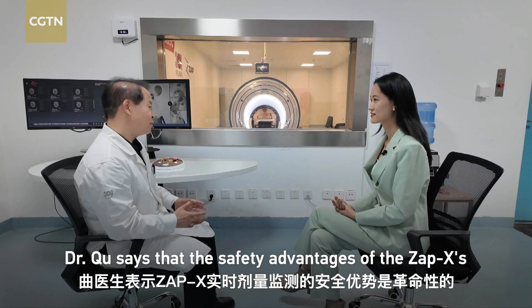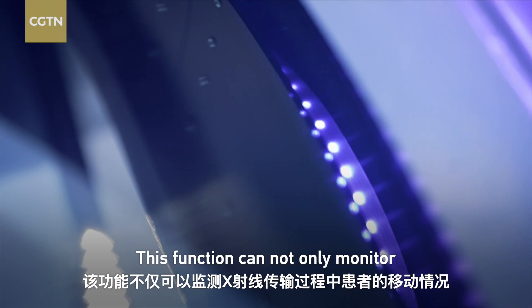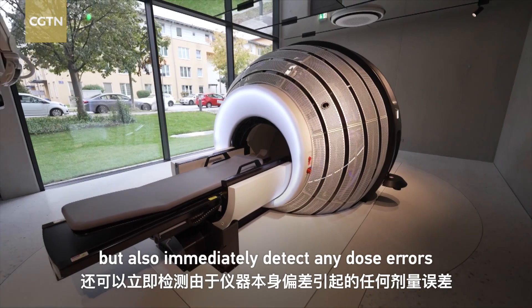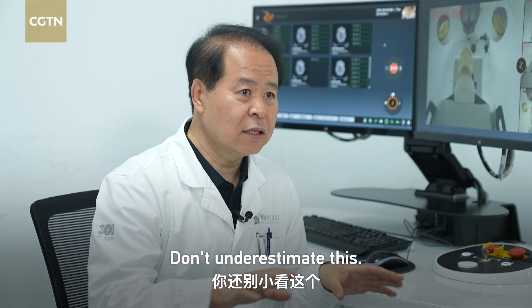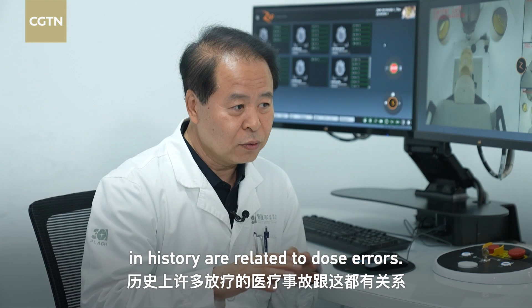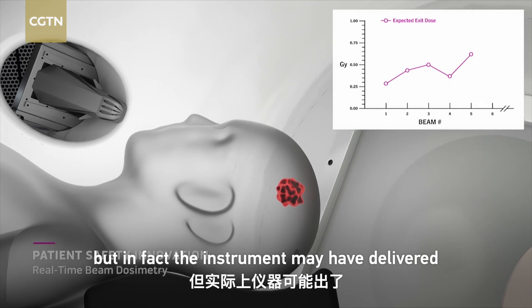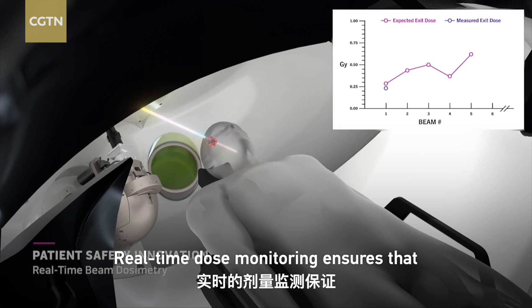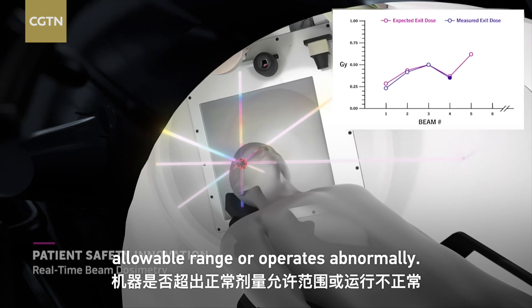Dr. Qu says that the safety advantages of Zap-X's real-time dose monitoring are revolutionary. This function can not only monitor patient movement during x-ray delivery, but also immediately detect any dose errors caused by deviations in the instrument itself. Many medical accidents caused by radiotherapy in history are related to dose errors — a patient should receive 2-gray radiation, but the instrument may deliver 5, 8, or even 10-gray with no monitoring. Real-time dose monitoring ensures doctors know immediately if the machine exceeds the normal dose range or operates abnormally.